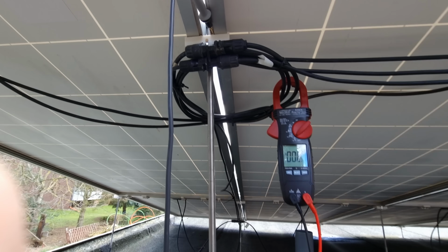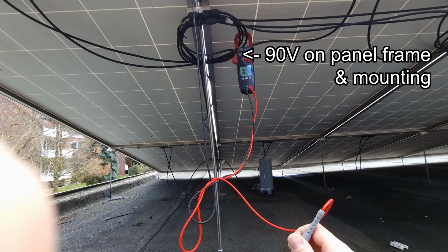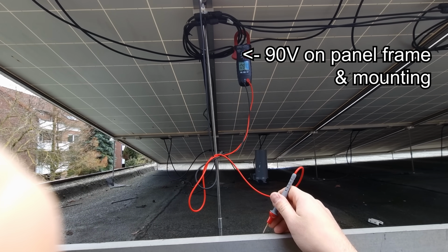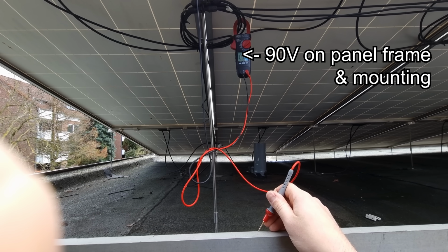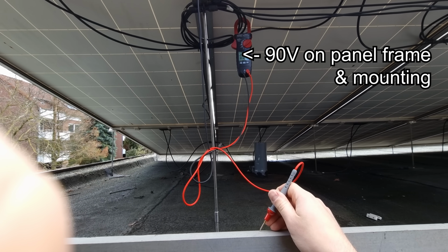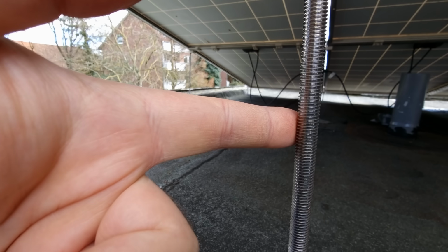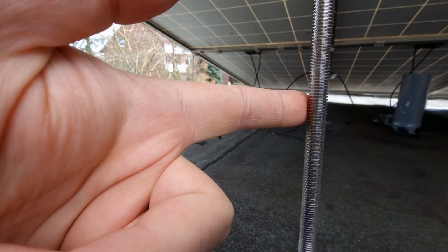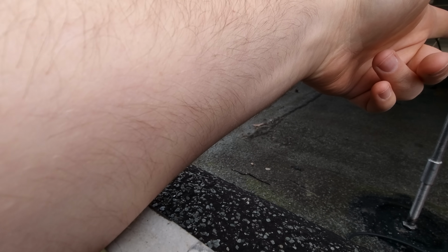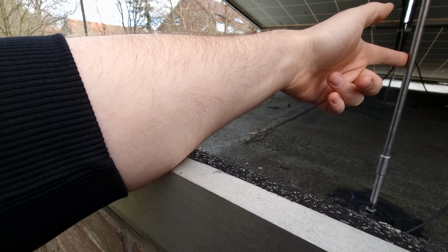And the final safety feature up here, protective earthing. This is primarily not about protection from a lightning strike. This is about ensuring that all touchable metal parts are at protective earth potential as code demands. There have apparently been cases where harmless low-energy leakage currents have given a worker nothing more than a startling little zap, but then that led to an involuntary movement and a neck-breaking fall from a roof. I'd like to avoid that if possible.